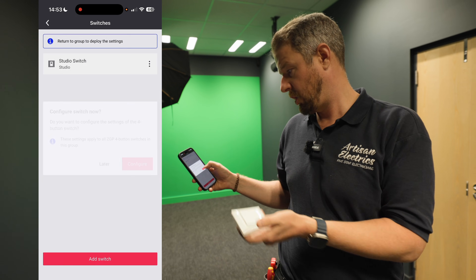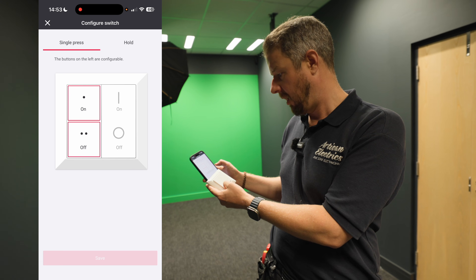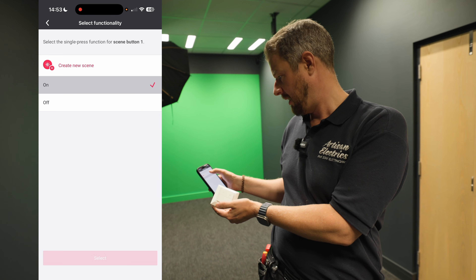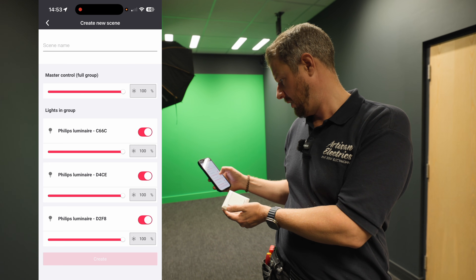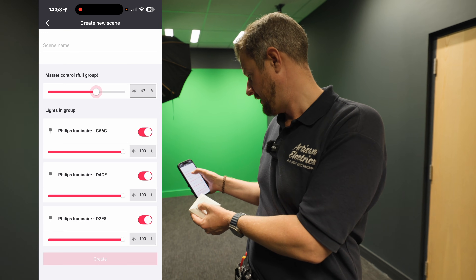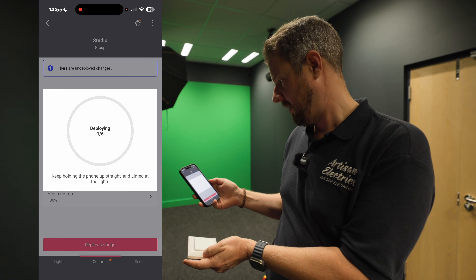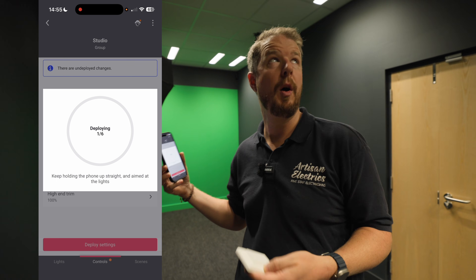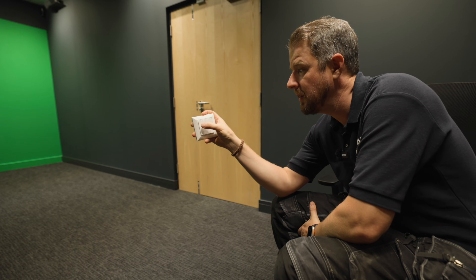To configure the switch, we can choose what the four buttons do. The buttons on the left are configurable for on or off, but we can also create scenes. For example, scene one could have all lights down to 20 percent. After deploying the settings to the lights, pressing button one dims to 20 percent, two is 60 percent, three is fully on, and zero is off. That is pretty impressive.